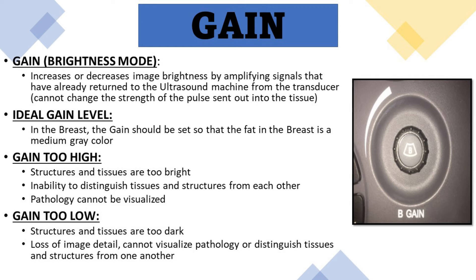When the gain is set too high, the structures and tissues of the breast are too bright, there's an inability to distinguish tissues and structures from each other, and pathology cannot be visualized. When the gain control is set too low, the structures and tissues of the breast are too dark, there's a loss of image detail, and you cannot visualize pathology or distinguish tissues and structures from one another.